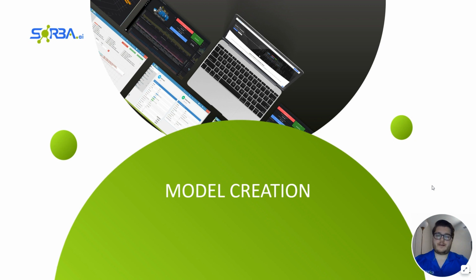Now, I am skipping a little bit of a step here, which is the data collection step. Once you have set up your data collection and ensured that the data is flowing properly, you would then typically wait 1 to 2 weeks in order to allow the model time to collect information from your asset before actually trying to create a model. This can be accelerated if you have historical information. You could bring that historical data set into the machine learning trainer in order to bypass this waiting time.